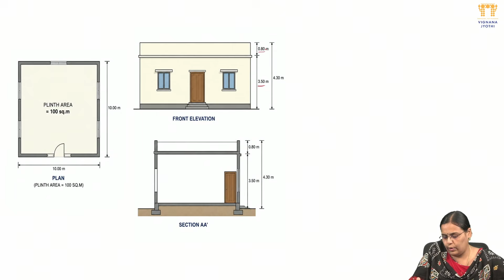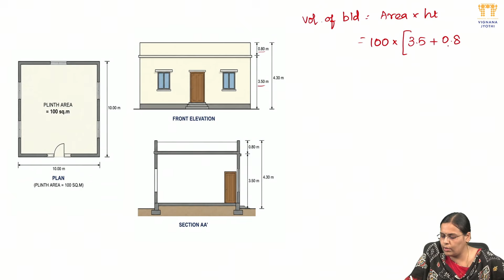So, volume of existing 100 meter square building is, so volume of building equal to area into height of building. So, area you know which is 100, and height we have to calculate to arrive at the volume. See, height of the building 3.5 meter plus this parapet wall, as I mentioned while explaining, you have to consider only half of the height, because at the parapet wall portion there is no roof. So, you have to only consider half of your height. So, 100 into 3.5 plus 0.8 by 2, which comes around 3.9. So, 100 into 3.9 would be around 390 meter cube. This is volume of your existing building.